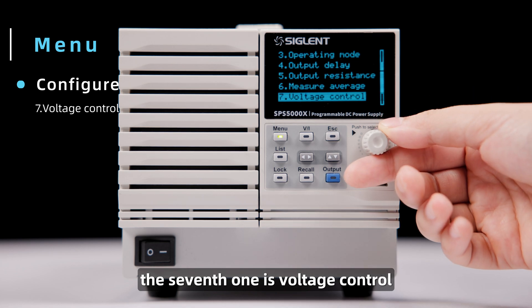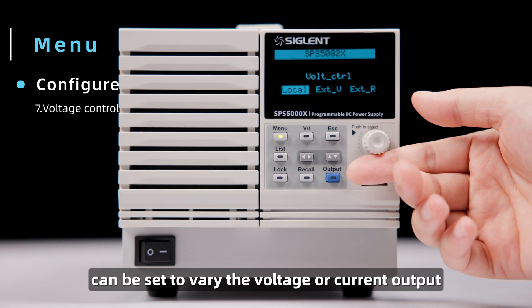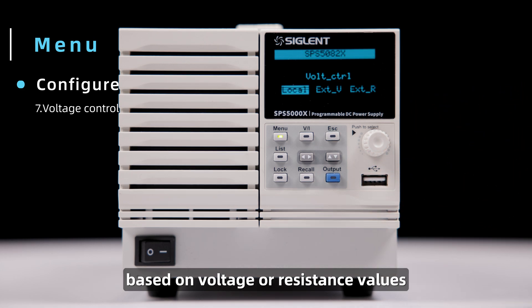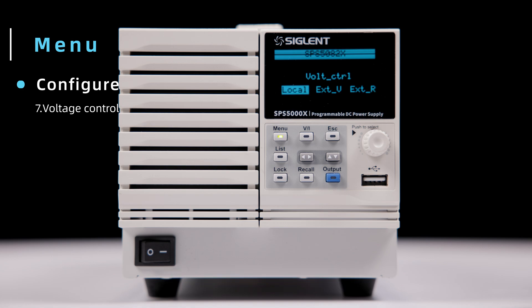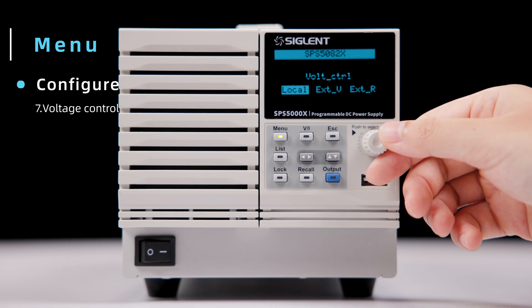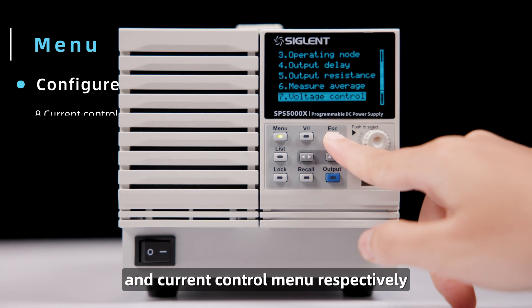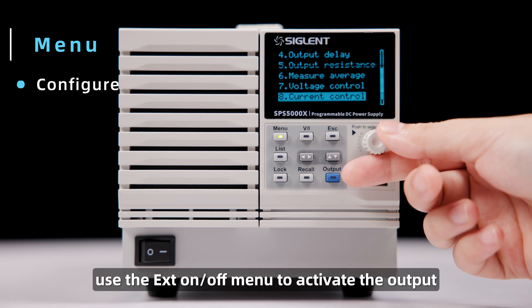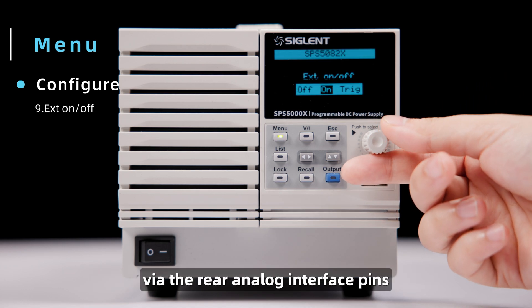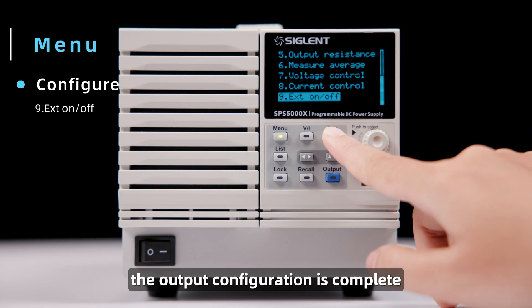The seventh one is Voltage Control. For more automated test configurations, the power supply can be set to vary the voltage or current output based on voltage or resistance values connected to the rear panel. This simplifies dynamic control of the output for industrial applications. Set the local or external control modes in the voltage and current control menus respectively. Use the Ext on/off menu to activate the output via the rear analog interface pins, which disables the output button on the front panel.